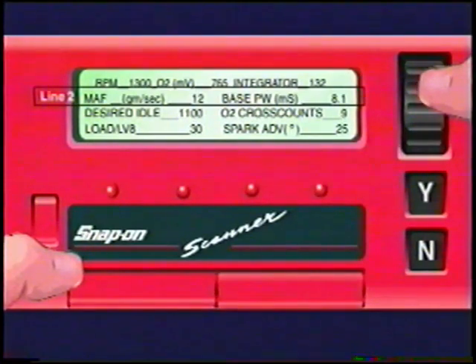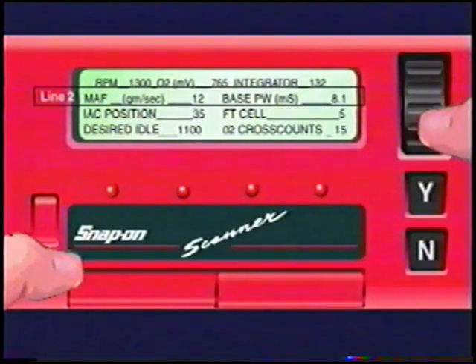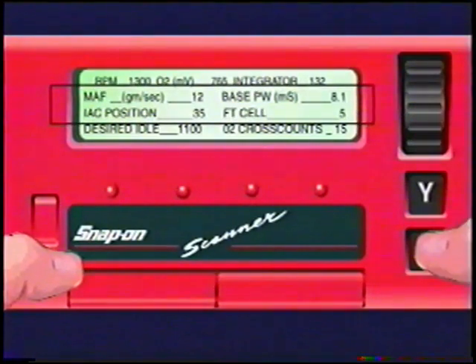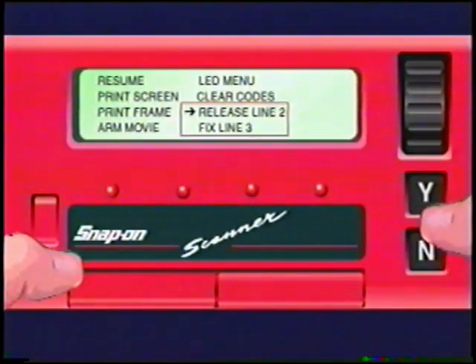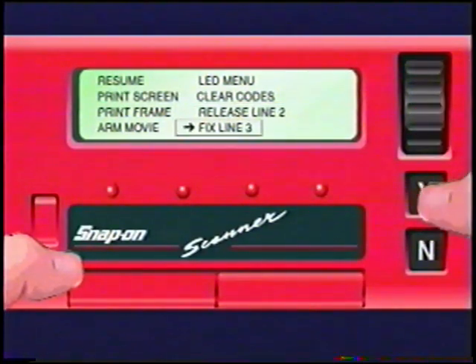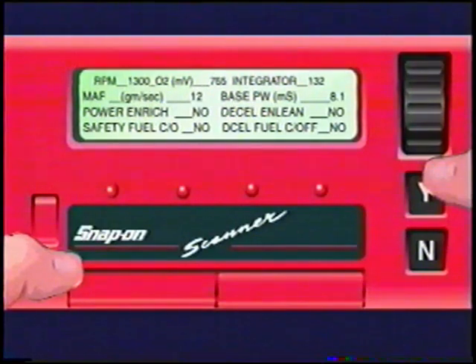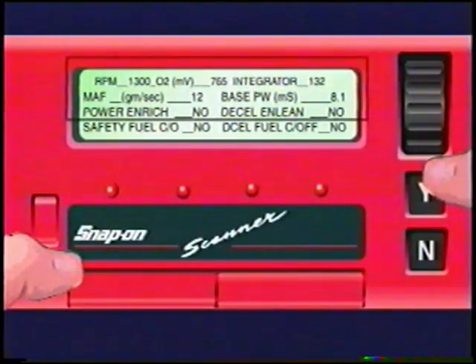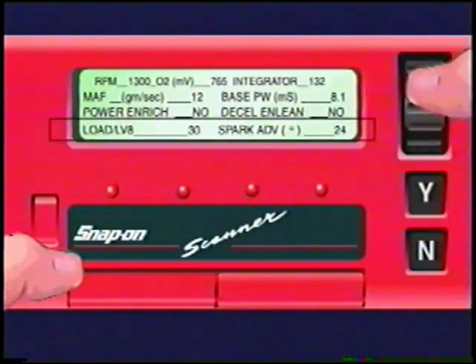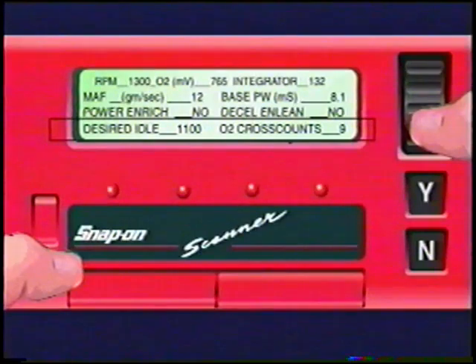Now when we scroll, only lines 3 and 4 change when we move the thumb wheel. Now we can fix line 3 as well. Hit the No button again to back up to the menu display. Here we see we have a choice to either release line 2 again or fix line 3 as well. Let's choose fix line 3 and hit the Yes button. This takes us back to codes and data again, and we can see that lines 1, 2, and 3 are now fixed in place. When we scroll, only line 4 changes.